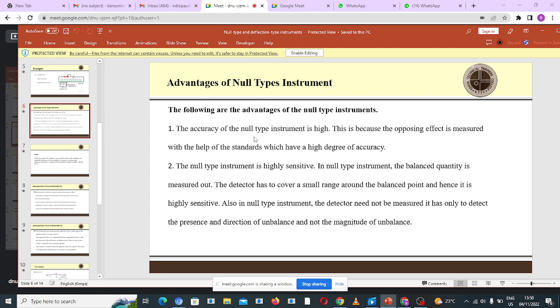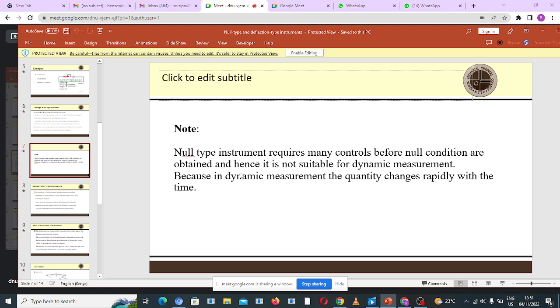Now let's look at the advantages of null type instruments. Number one: the accuracy of null type instruments is high, because the opposing effect is measured with the help of standards which have a high degree of accuracy. Number two: null type instruments are highly sensitive, because the balance quantity is measured and the detector can cover a small range around the balance point. However, null type instruments require many controls before null conditions are obtained, and hence they are not suitable for dynamic measurement, because in dynamic measurement the quantity changes rapidly with time.